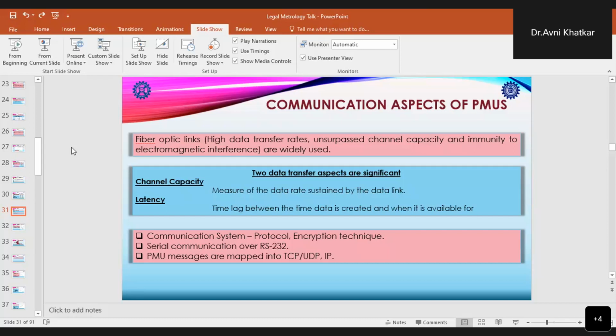When we talk about communication aspects, two data transfer aspects are also very significant. That is channel capacity, which is nothing but the measure of the data rate sustained by the data link, and the latency in the measurement. Latency is the time lag between the time the data is created and when finally it is available. So these two aspects are very significant from the communication point of view of the phasor measurement unit. And when we talk about the communication system, all the protocols and encryption techniques also come into the picture. So when we have PMUs, the communication is serial communication using RS-232, and all the PMU messages are mapped into TCP, UDP or IP.